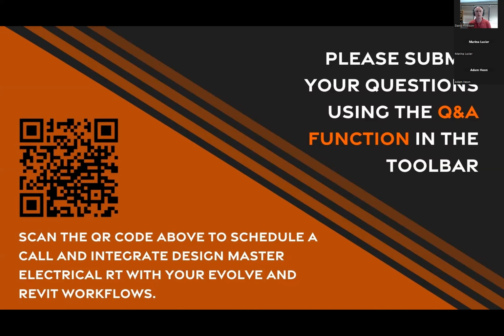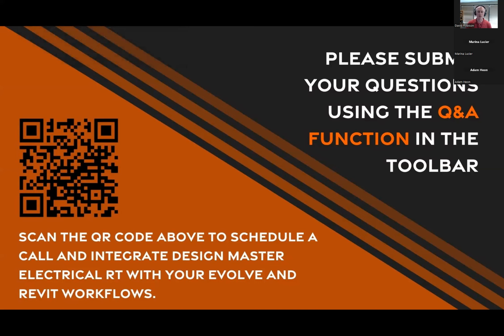You actually need to go into our software, go into our panel edit command, make the change there. And then our software knows that you made the change and can go make it everywhere and update everything. So it's not bi-directional in that sense. You don't make the changes in your schedules. You always go back to our ribbon, our interface, and make the change there. And then it knows that that was a change that you meant to make and to get it right. Because Revit's a little limited in what they let you do with your shared parameters. So we've got a lot of stuff going on where if you made a change, it wouldn't be clear if that was an intended change or if it was one of our various options. So we have to make the change through our interface.